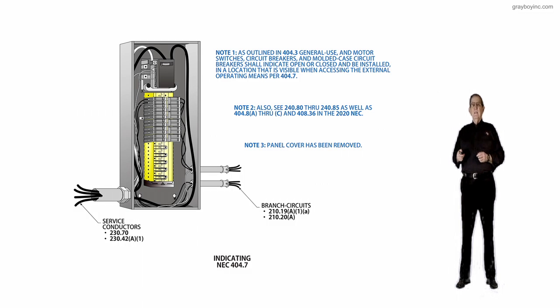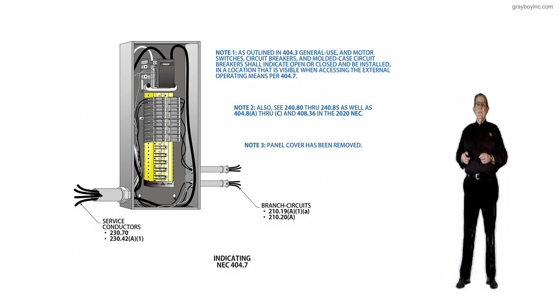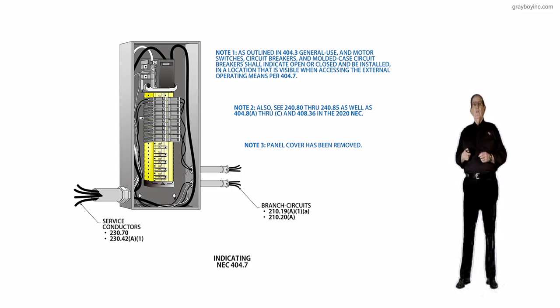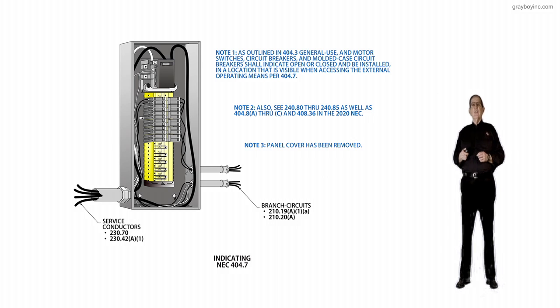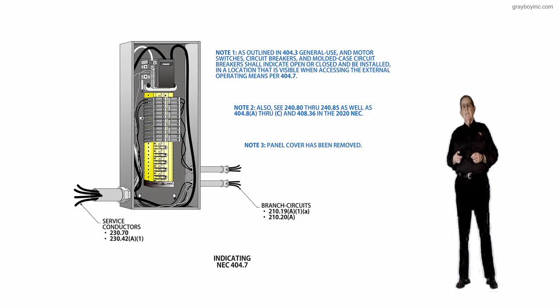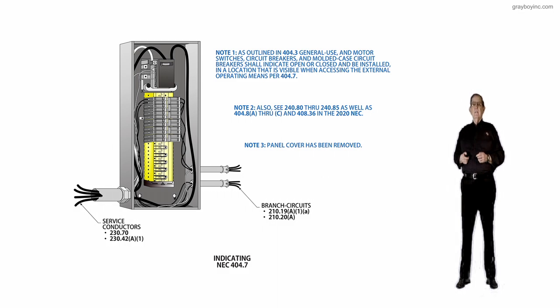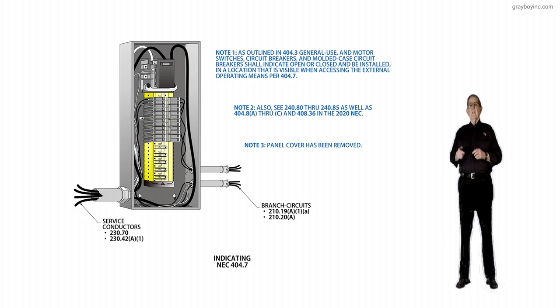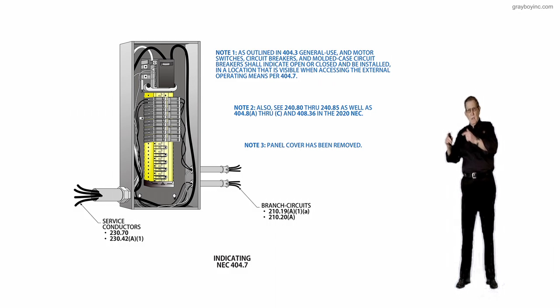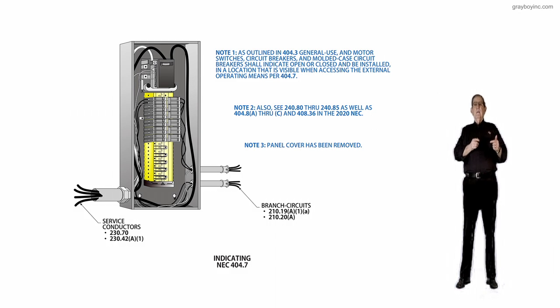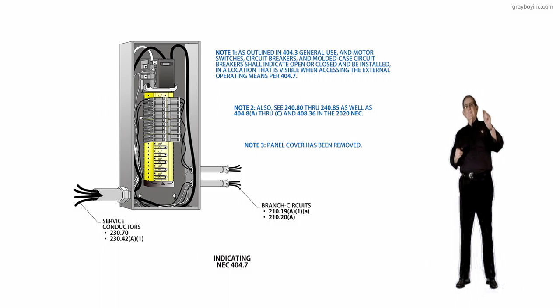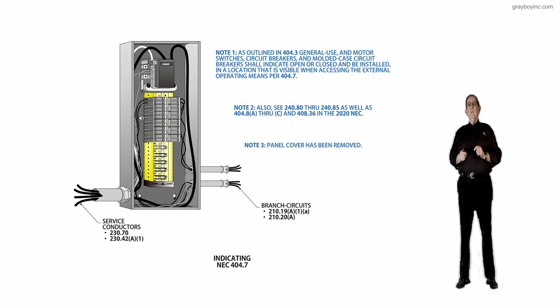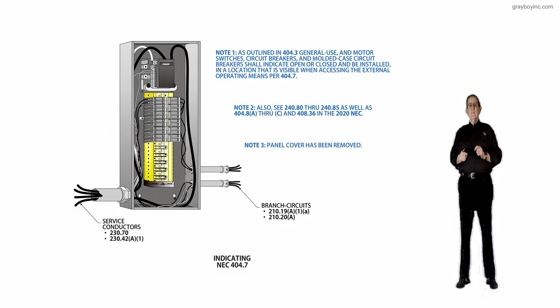And then it lists 210.20A that sizes the overcurrent protection device ahead of these conductors where they receive their supply. Notice that the conductor has to come along at 125% to derate the breaker 80% for loading when you're dealing with continuous type load.